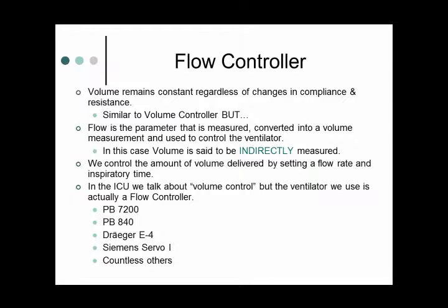So even though we're controlling flow, the volume is also fixed. It's also a volume-oriented breath. But in the ICU, those ventilators, all 3 of the ones that we learned, or that you were playing with, are really flow controllers. They're not dual. Well, when they're in a volume-oriented mode, they are flow controllers. When they are in the dual mode, that's a pressure-controlled breath, because the pressure is fixed for the duration of that breath.